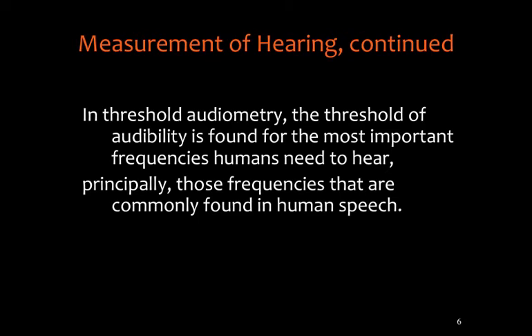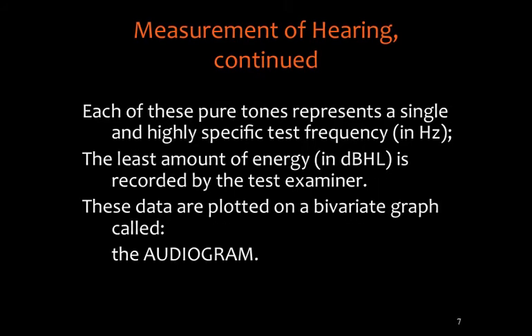Basic pure tone audiometry does not provide information regarding our perception of duration of sounds. In fact, duration is maintained as a constant on a typical audiometric test — the presentation duration needs to be at least 300 to 500 milliseconds or longer, as any shorter duration will alter the test outcome and make the audiogram appear poorer. When we assess pure tones, we measure the least amount of energy in decibels required for a person to respond. When we find that value at a specific frequency, we plot it on a two-variable graph called the audiogram.